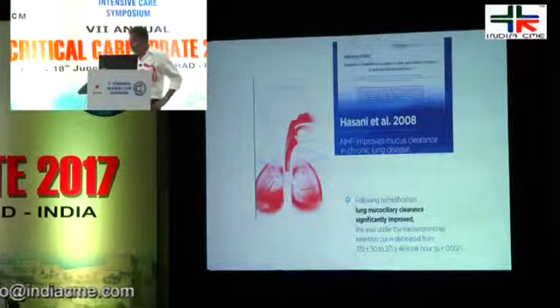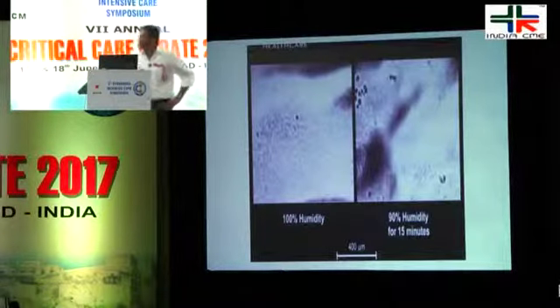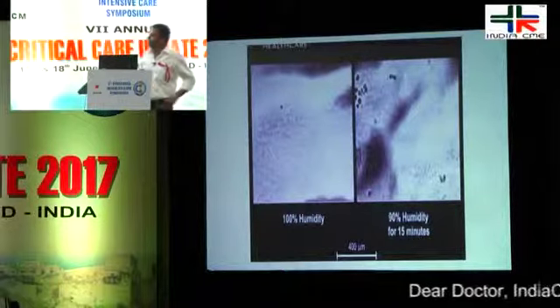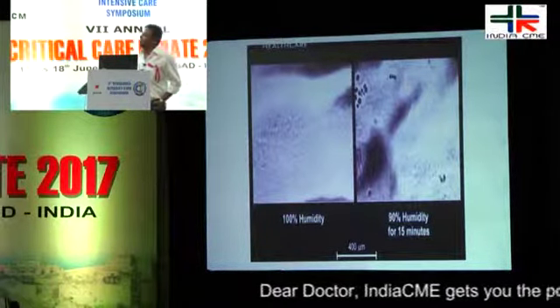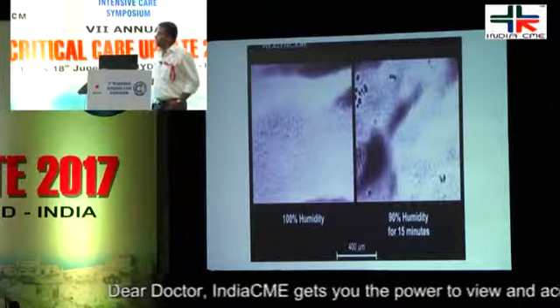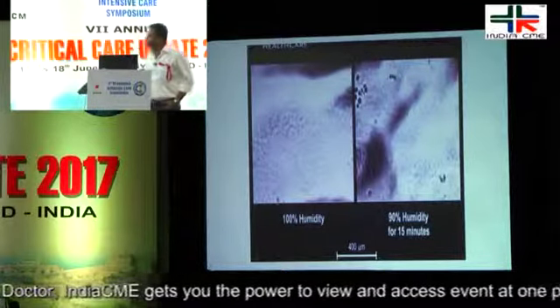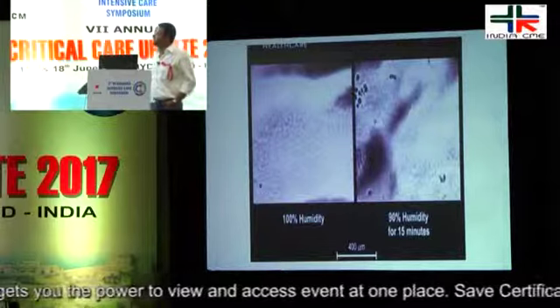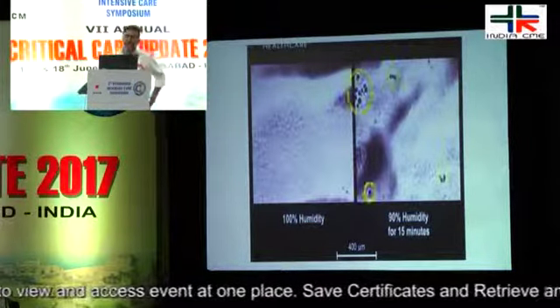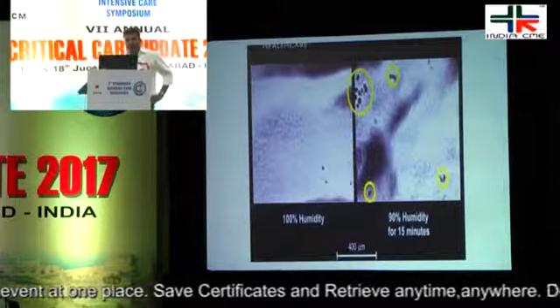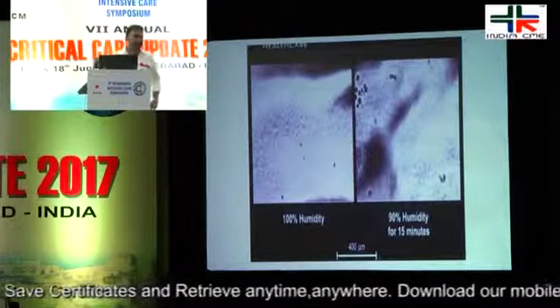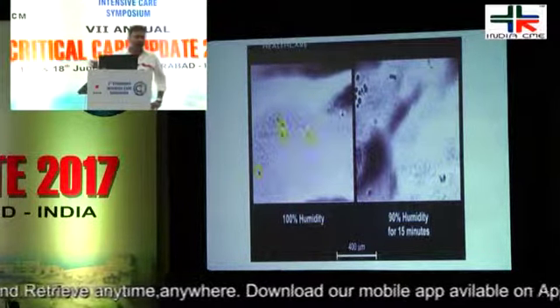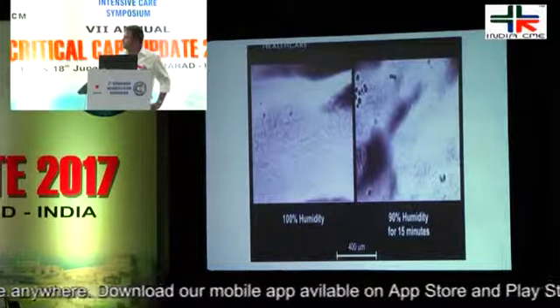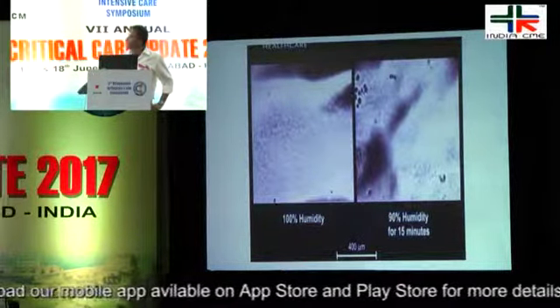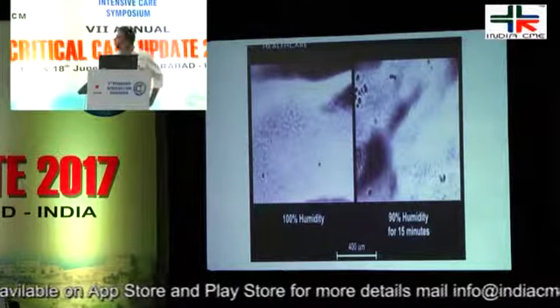So, what HFNO does is improve the lung mucociliary clearance, and let's see this video. You see, with 100% humidity, look at the cilia as well as the mucous membrane. With only a 10% drop in humidity for 15 minutes, see the speed of mucociliary clearance has gone down. So, for effective mucociliary functioning and clearance, you need warm and humidified air. You can pretty well see the movement is fine here, whereas these are all stagnant over here.